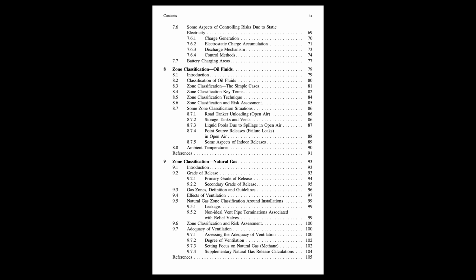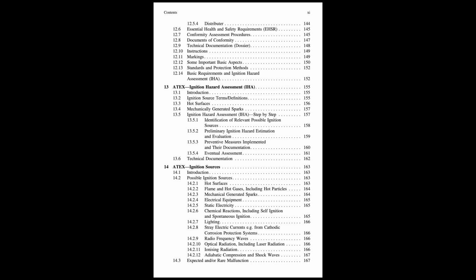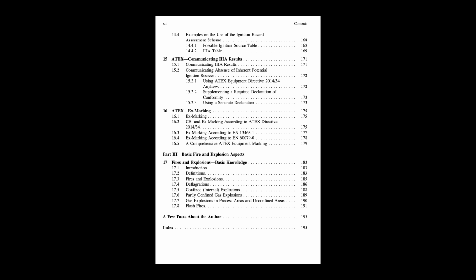We dig a bit deeper. As we said, they define the concentration range where ignition is possible. But the guide emphasizes these aren't fixed constants. They can change, primarily with temperature and pressure. How so? Generally, higher temperatures and higher pressures tend to widen the flammable range. They might lower the LEL slightly and raise the UEL, meaning there's a broader range of concentrations that can ignite. Making ignition easier, essentially. Correct. The LEL in particular is a really critical value used when defining those hazardous zones we'll talk about later.